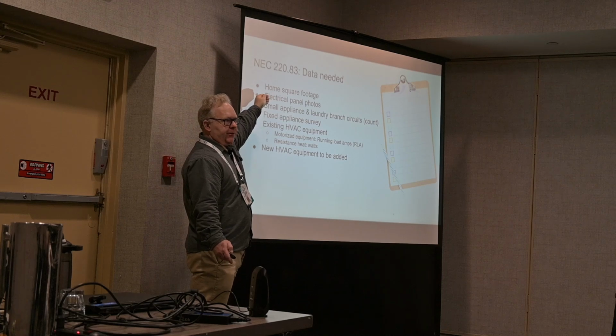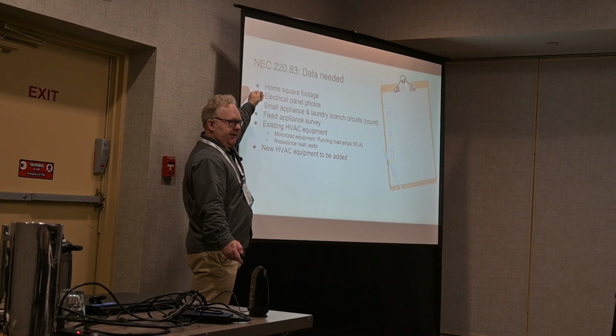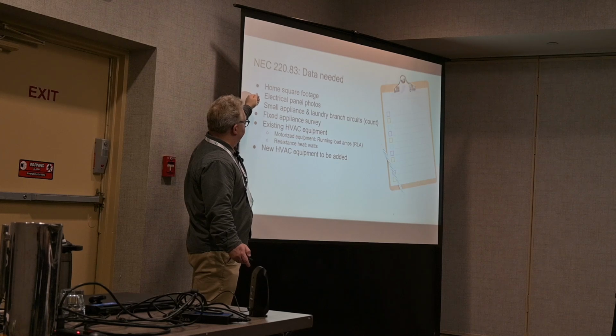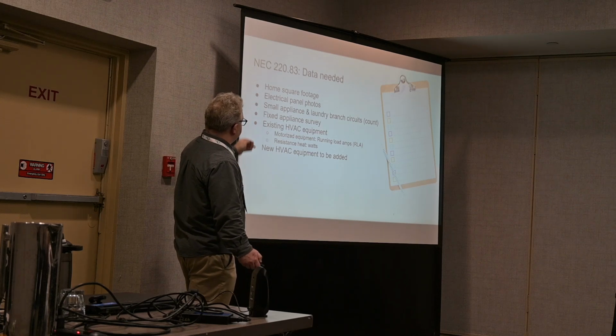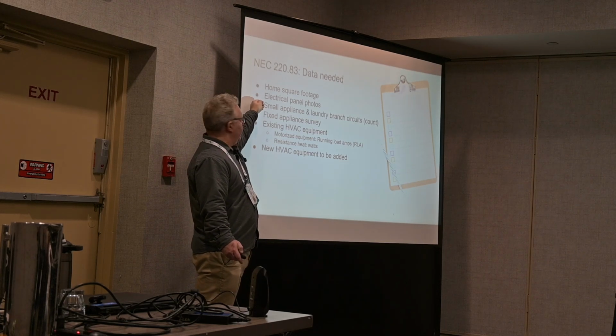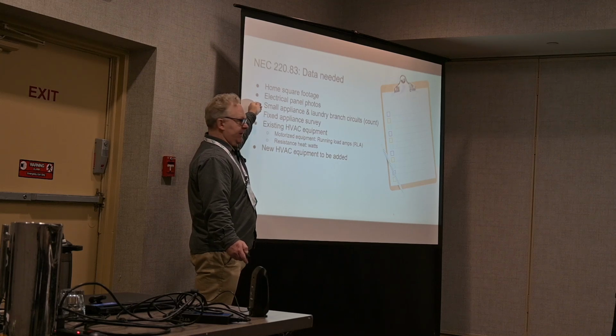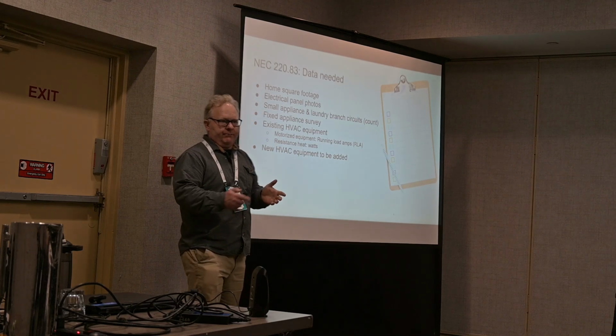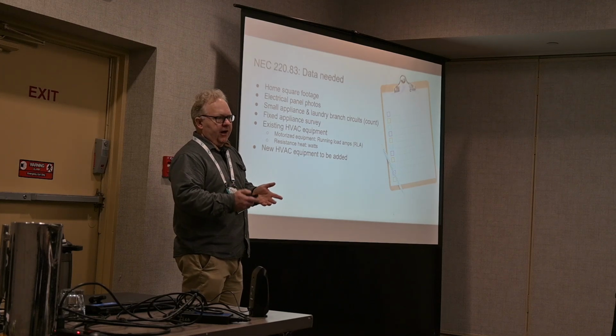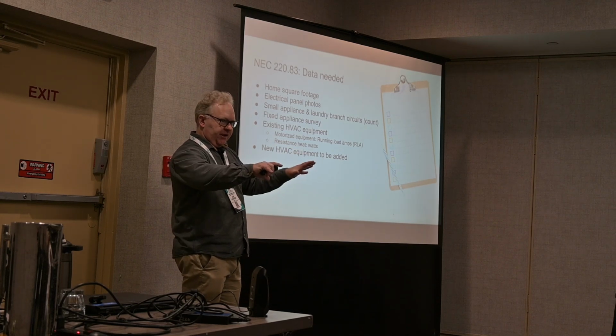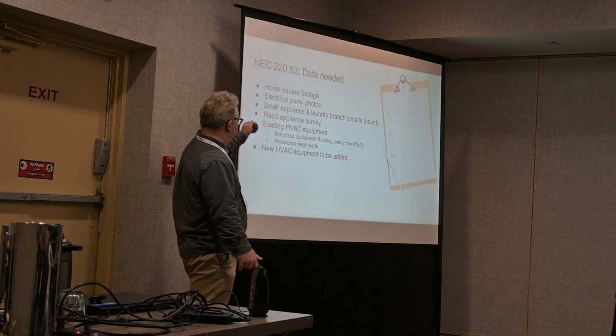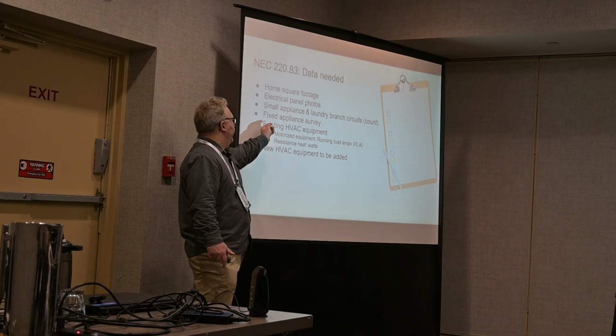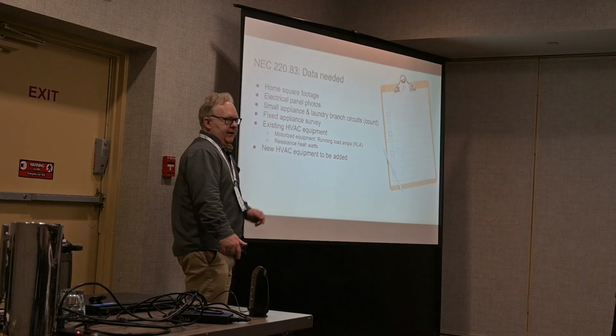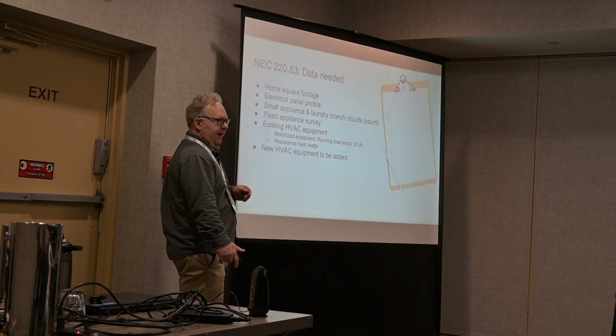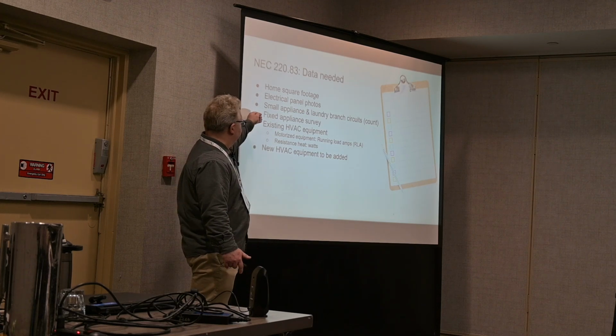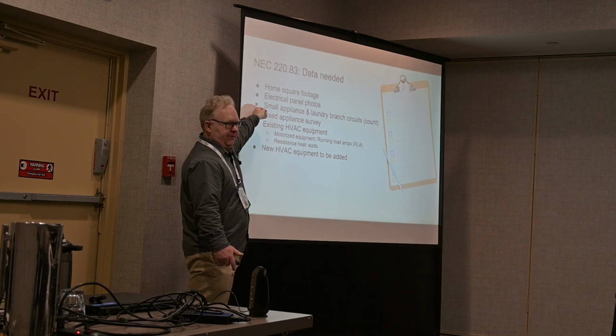Electrical panel photos, and I'll show you in the next slide exactly what we're going to need to find from those. We need to know the number of small appliance and laundry branch circuits. These are typically 20 amp ground fault circuits like you'd have on your kitchen countertop and in your laundry room. The one thing that you're probably not doing as a standard energy audit that you'll need to add is a survey of the fixed appliances.